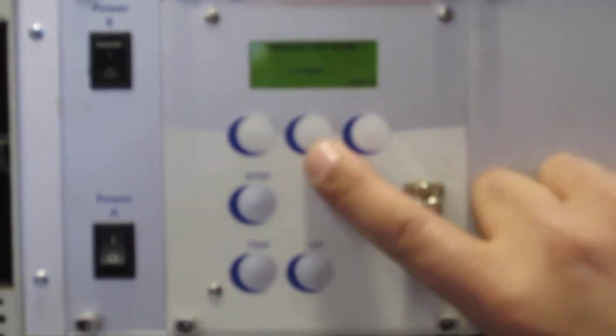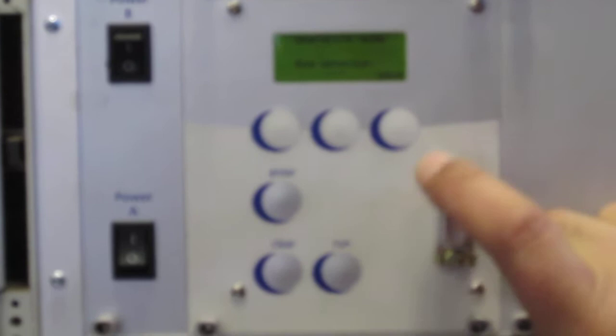This case, we're doing a rod detector. Because we have a rod detector, it's going to give us up to 25 points on that rod detector. We can still do an open and a close, we can still do a full and an empty, but we're just going to do 2 points. The rest of the points after that, when we go into the calibration mode, we'll put 0 in the third point, and it doesn't use the rest of the points.